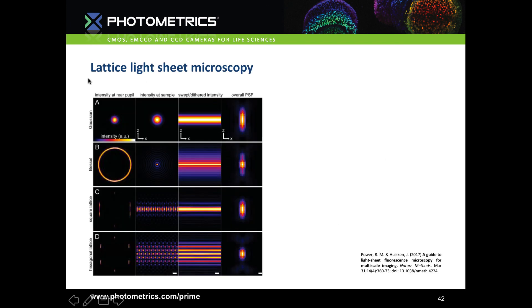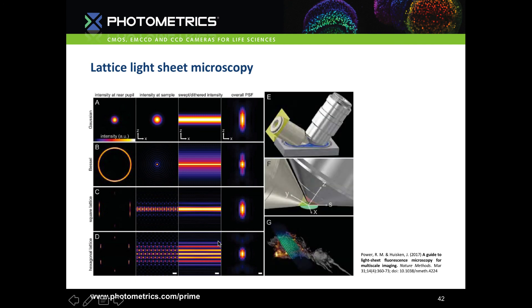Bessel beams have made possible the last type of lightsheet: lattice lightsheet, developed by the Betzig lab. It combines Bessel beam illumination with structured illumination microscopy by creating a patterned Bessel beam — shooting the beam through a grid to create many little Bessel beams producing multiple thin lightsheets. This gives a two-fold increase in resolution like in SIM but highly parallelised, making the system incredibly fast with speeds of up to 1000 frames per second. It's a very complex system but unmatched in resolution and speed.